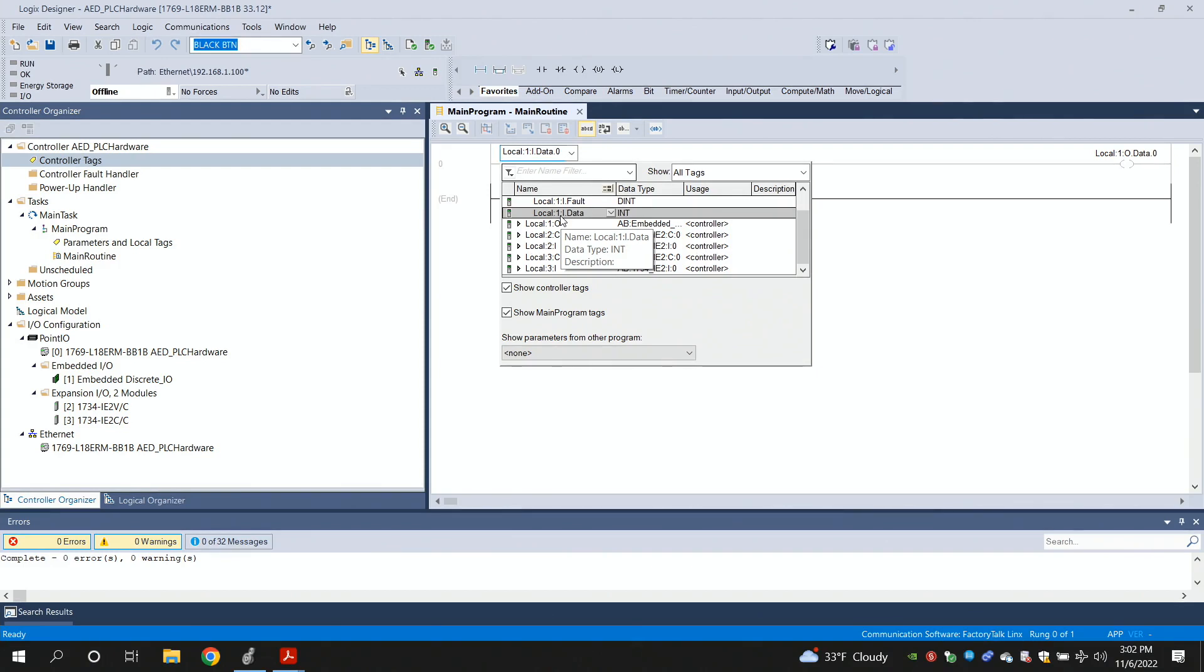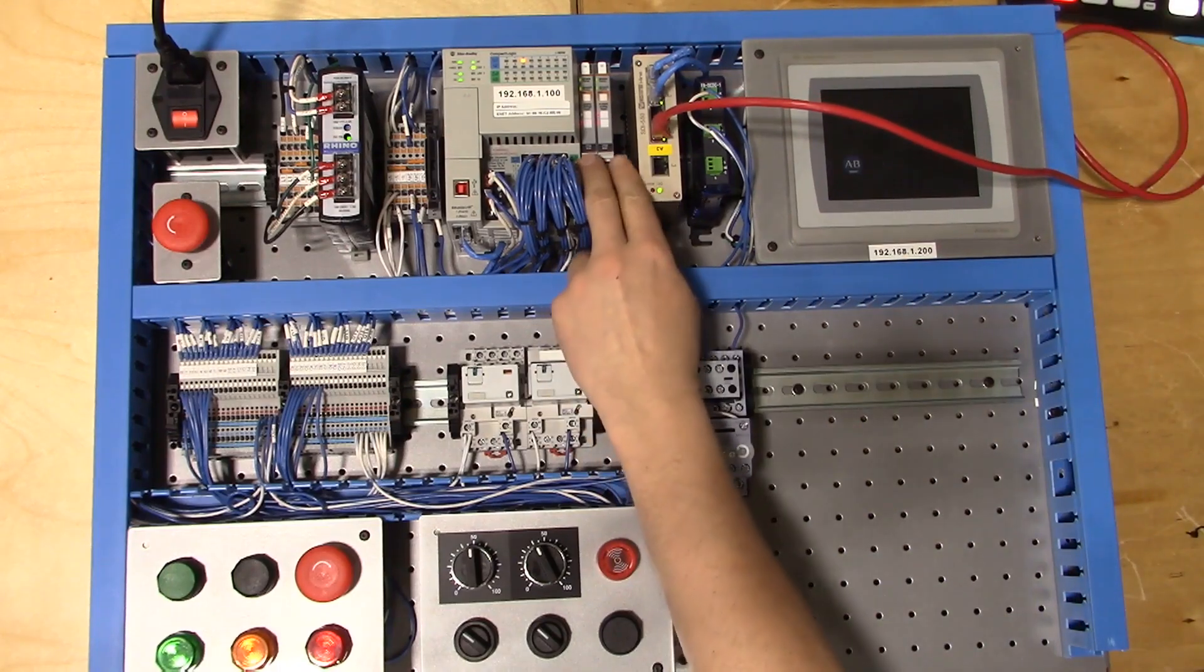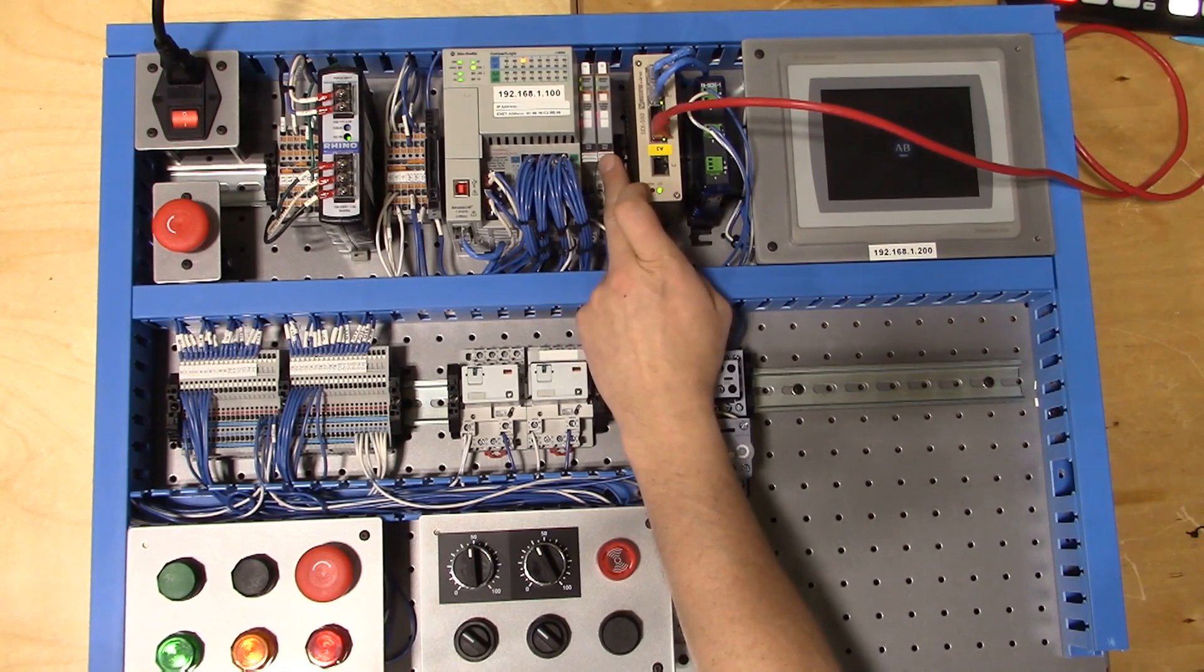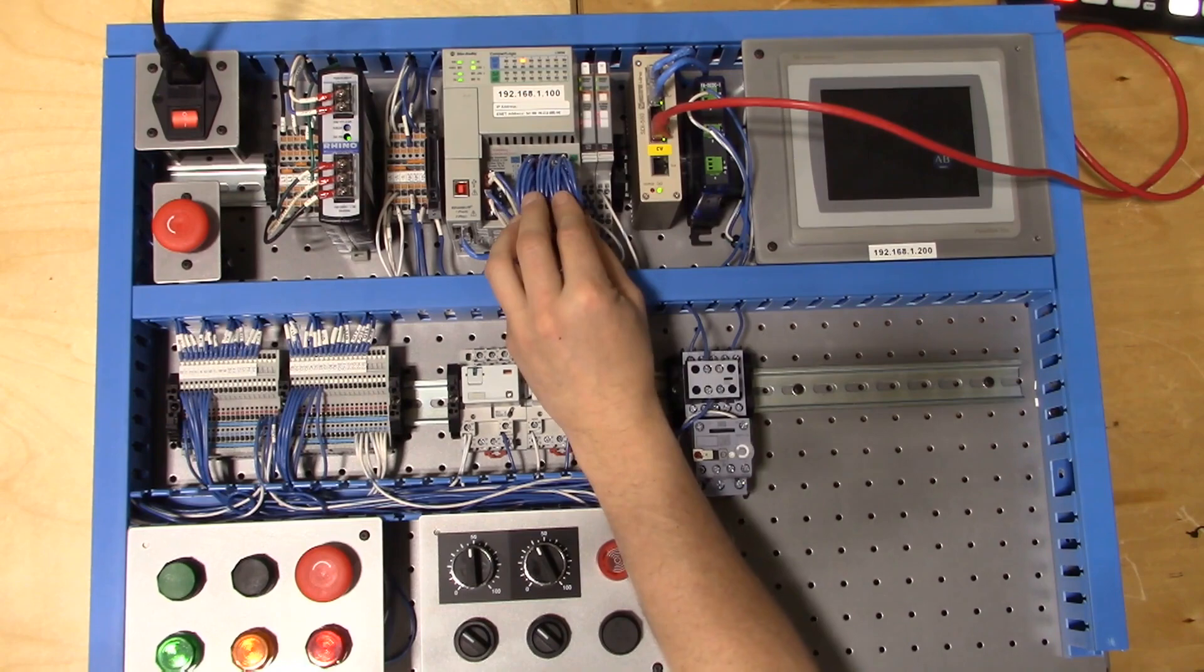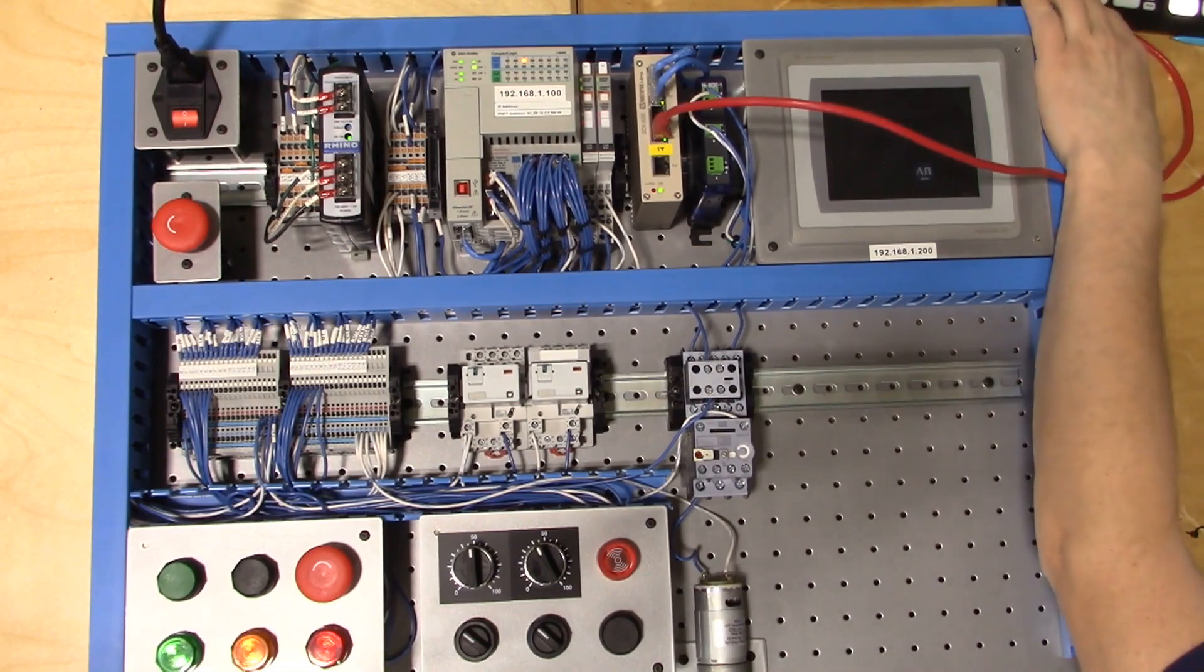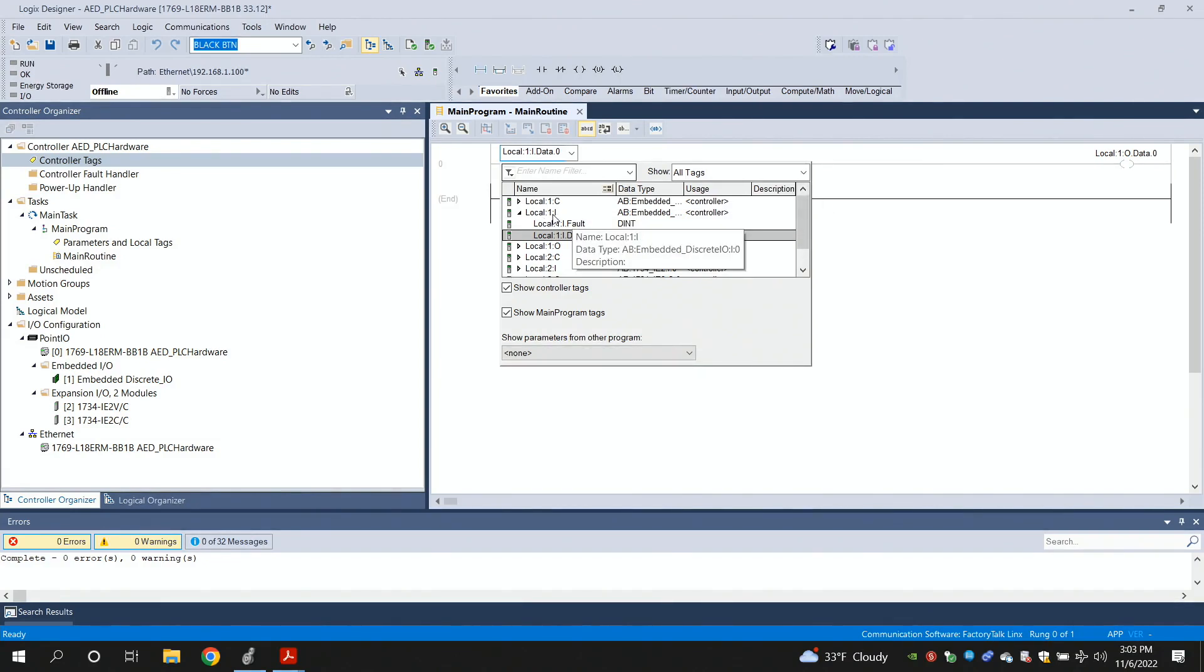This is a local slot number 1, which would be the embedded inputs and outputs. Embedded means that they're just built into the PLC, as opposed to being an expansion or a module that you'd add on over here. Embedded means they're integral, they're all included in the same part number here. Those are built-in ones, and they have to occupy slot 1. That's why they're showing up in our software over here as such. Local slot 1 inputs. These are the embedded inputs for our PLC.